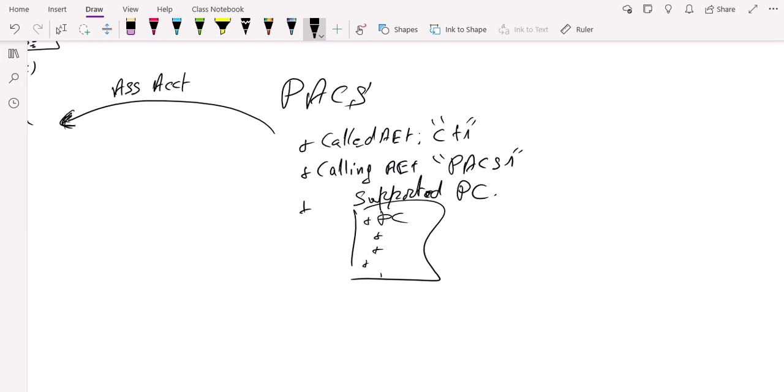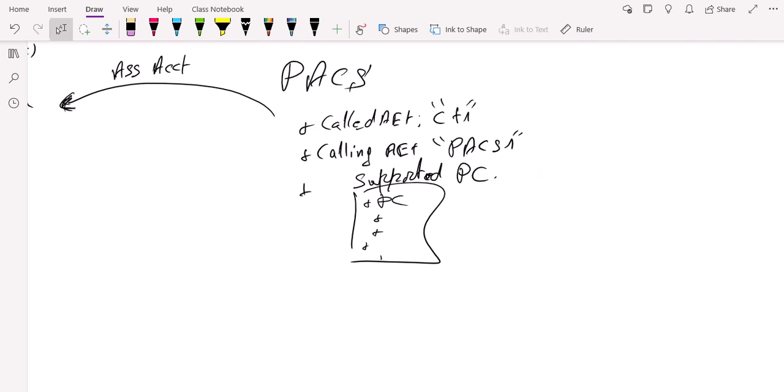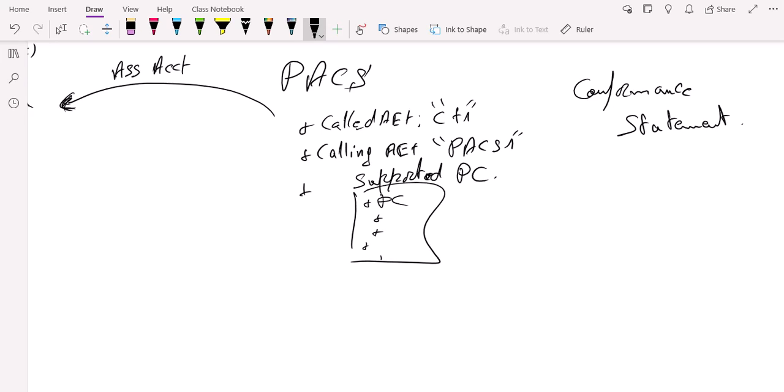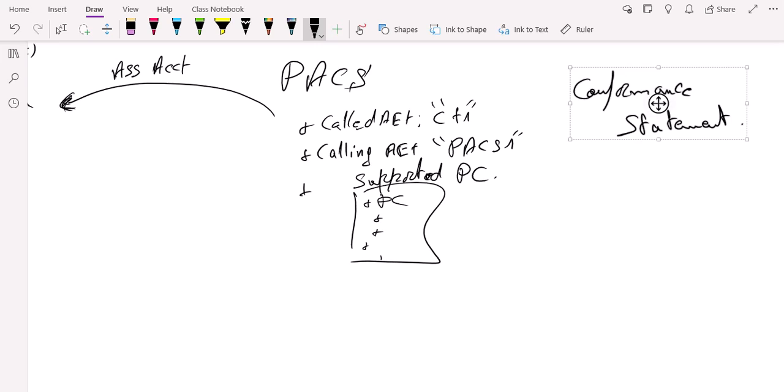And by the way, if you want to access the services that are supported by any DICOM device, PACS or CT scan or any DICOM device, you can look for its conformance statement. It's like a detailed technical document companion most devices that outlines exactly which features of the standard are supported and you can access it just by Googling the conformance statement and including the name and the version of the device you want to check. And then you can find it really easily on internet. So that's the conformance statement.